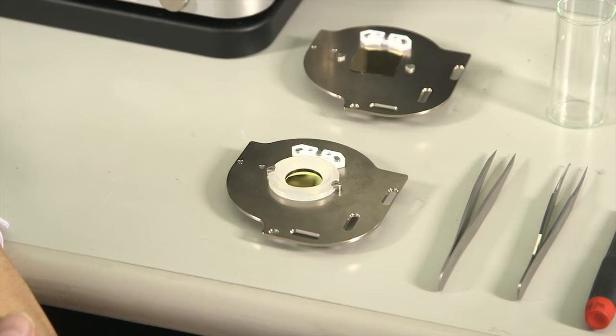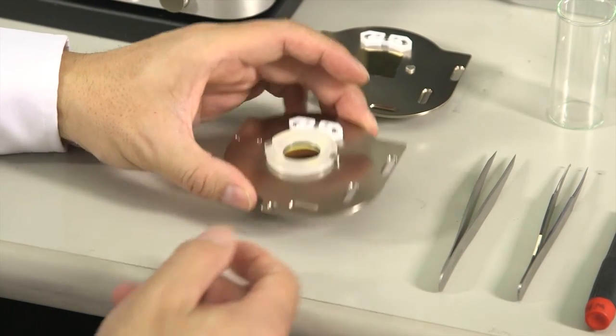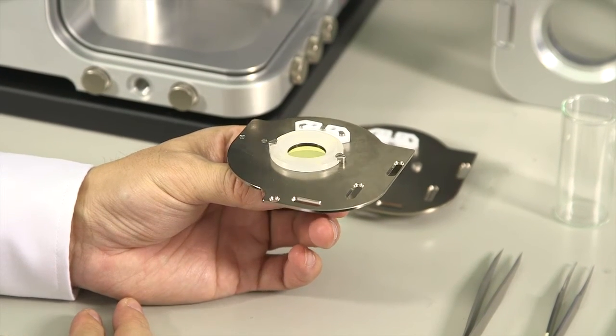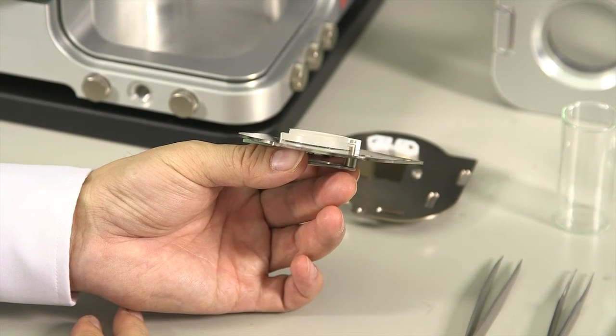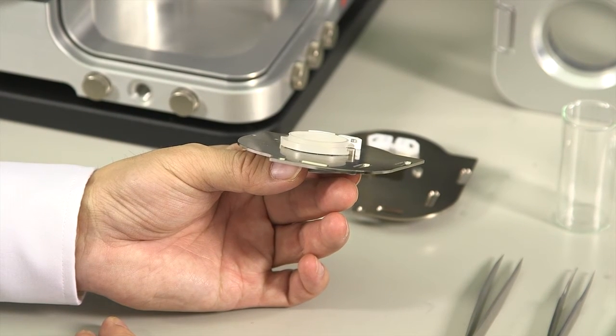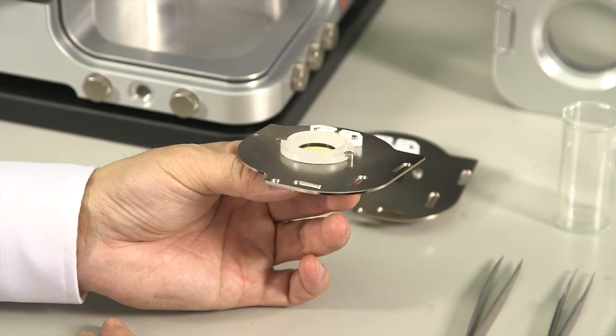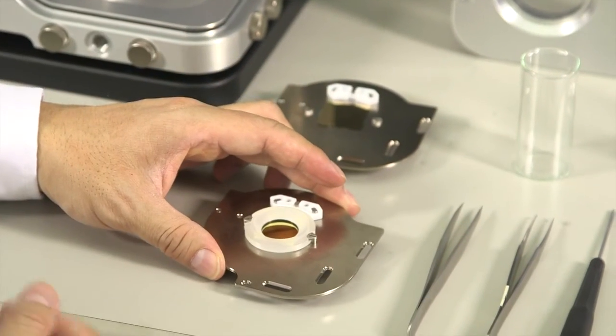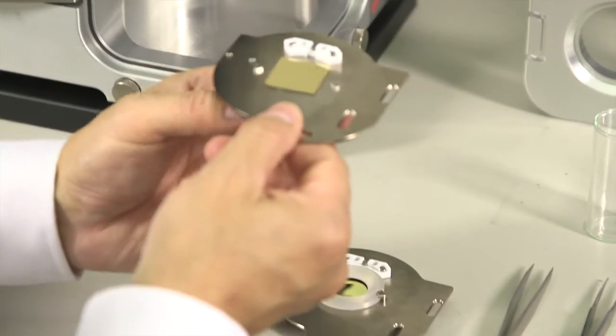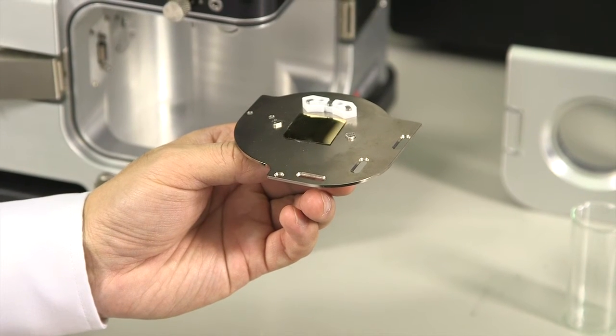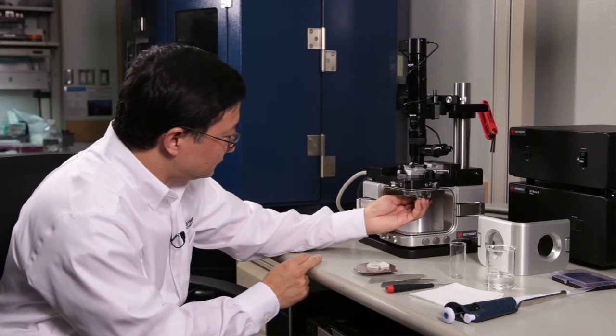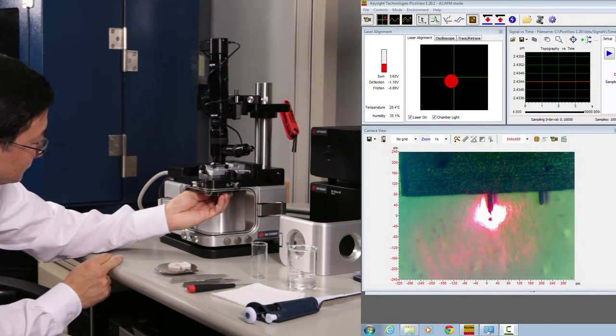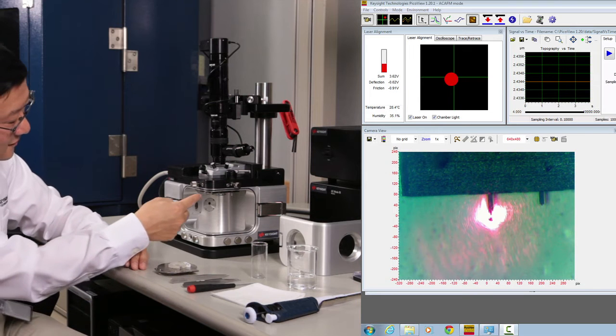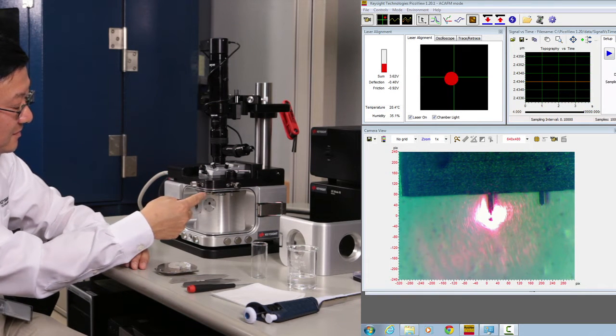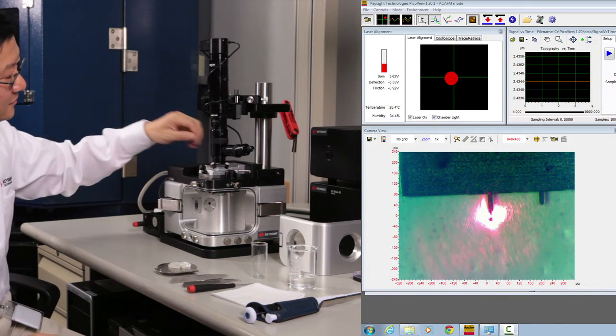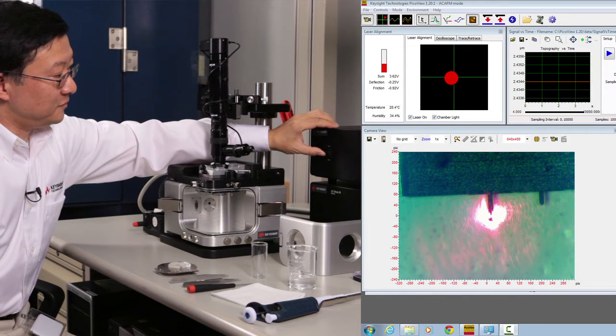Now, before we mount the sample onto the AFM, let's take a look at the sample. With the liquid cell on, you can see the side view of the sample is blocked by the liquid cell, and therefore you cannot judge the distance between tip and sample, and it's very difficult to do rough approach. That's the reason we need to have another sample stage with a similar sample thickness on it to do a pre-alignment. Now, from side view, with the help of this lens, you can see the distance between tip and sample. So you can use this manual switch to move the sample close to the tip.